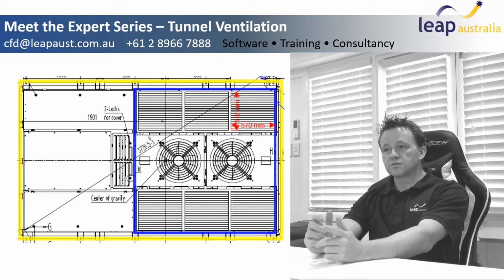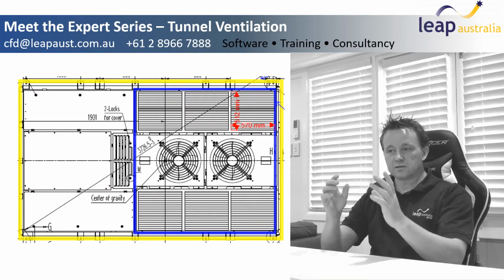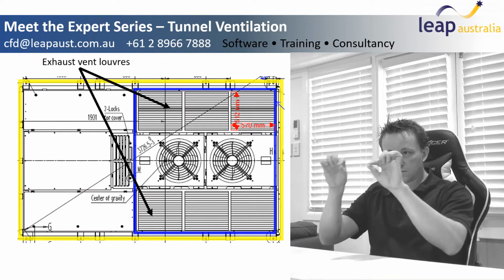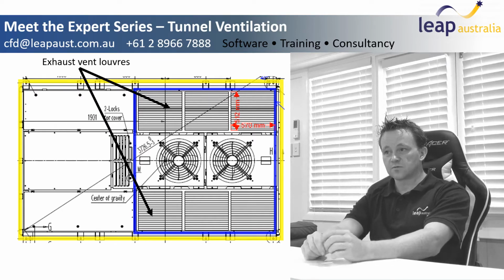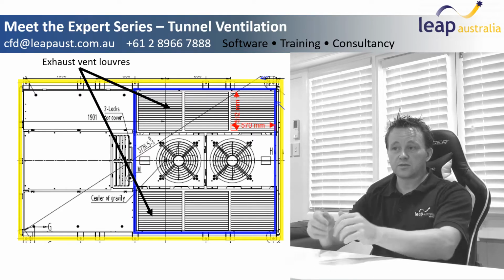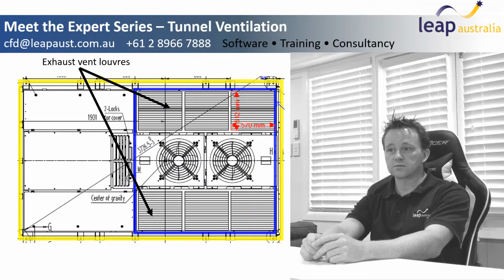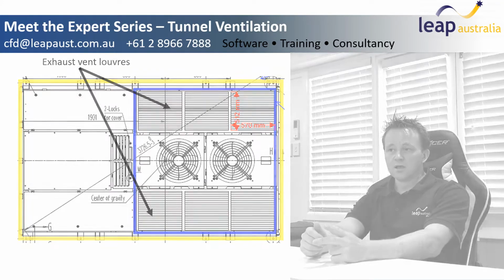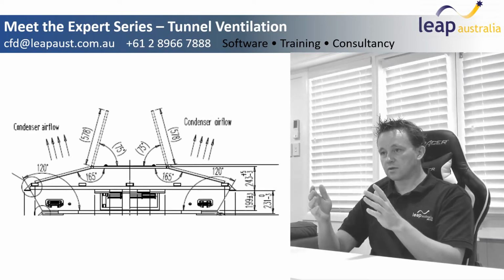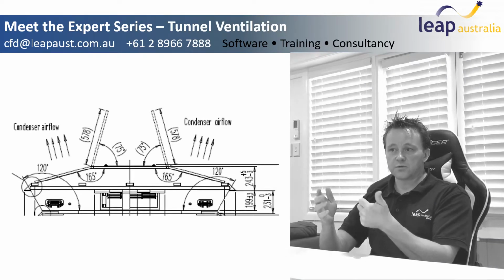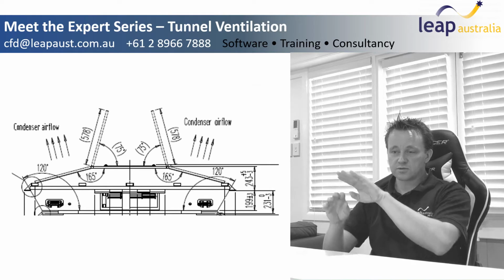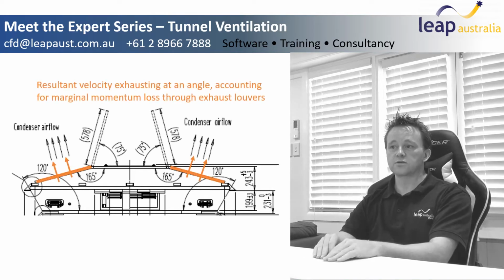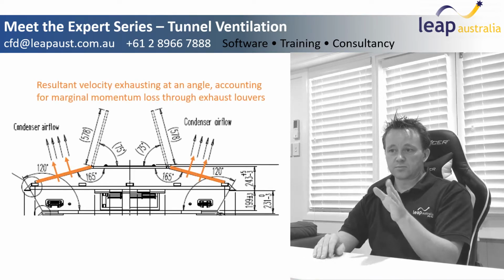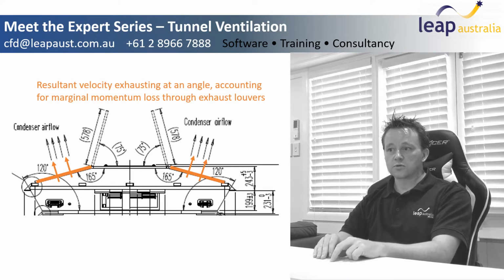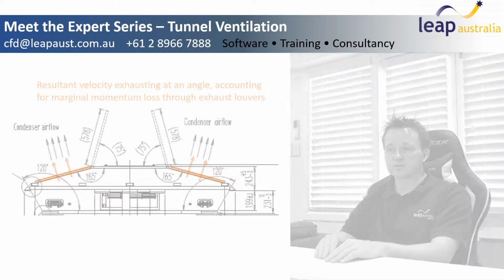The vents themselves were actually quite detailed. They had a number of louvers, and so it was considered for this case, where we were modelling a long tunnel with 8 cars, that it was going to be very expensive to model those explicitly. We worked out the flow direction for each of those, so there's the straightened flow that will be passing through those louvers. We were able to put in direction controls as boundary conditions there, and that enabled us to specify the inlets.